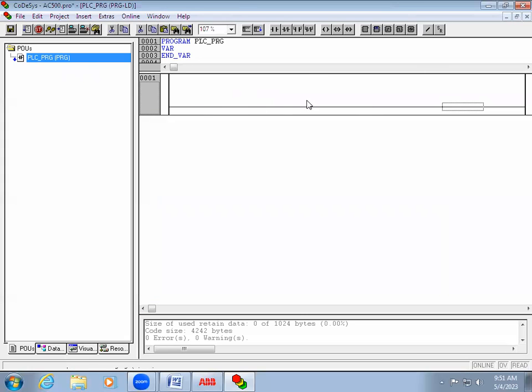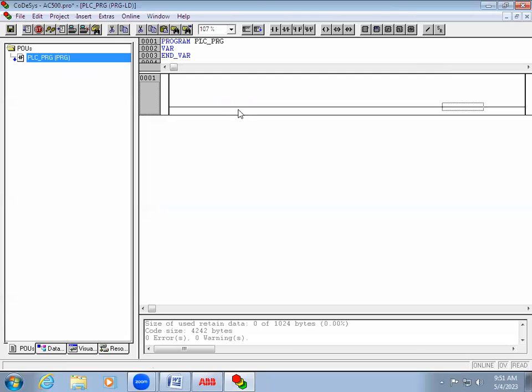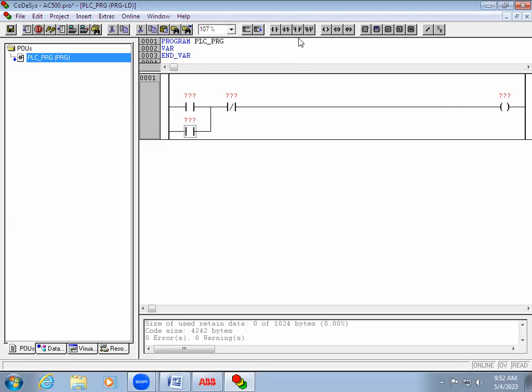Double-click to open the Ladder Diagram and develop the program. You can see the basic symbols. Each line is called a Network — in some PLCs it is called a rung, but here it is called a network. When you right-click you can insert a network either before or after. We'll try to do a start/stop operation to get familiar with the software. I'm placing a normally-open contact. When placing a coil, note that in ABB after placing a contact, the cursor stays on that contact — always select the line before placing the next symbol.